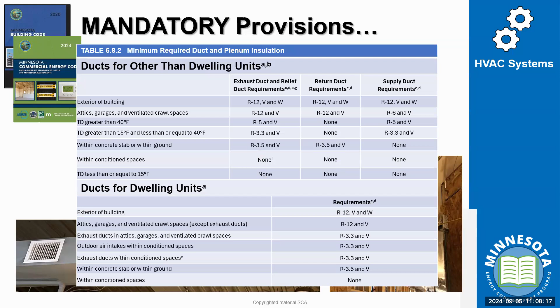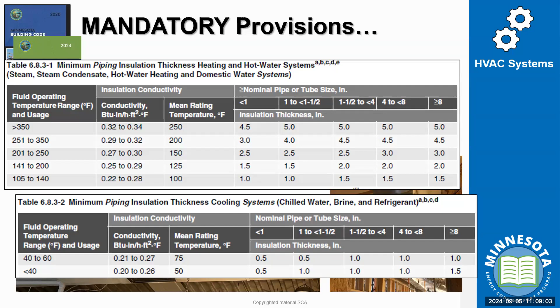insulation values. We see that with piping insulation associated with refrigerated lines, whether we're using that for, again, heating and cooling steam systems, right? We want to make sure that we're thinking about that pipe insulation. Remember, pipe insulation is not necessarily there to maintain the temperature as much as prevent the chilling impacts or overheating impacts of the actual pipe itself, right? The 1 inch or a ½ inch of insulation is not going to maintain the huge temperature swings.